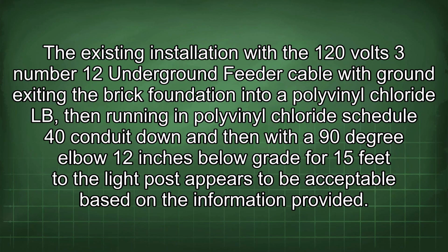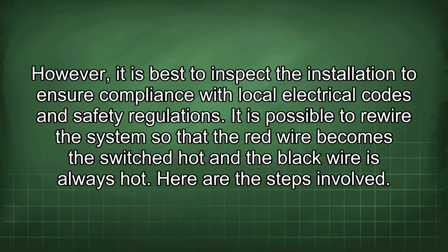The existing installation with the 120 volts 3 number 12 underground feeder cable with ground exiting the brick foundation into polyvinyl chloride LB, then running in polyvinyl chloride schedule 40 conduit down and then with a 90-degree elbow 12 inches below grade for 15 feet to the light post appears to be acceptable based on the information provided. However, it is best to inspect the installation to ensure compliance with local electrical codes and safety regulations.